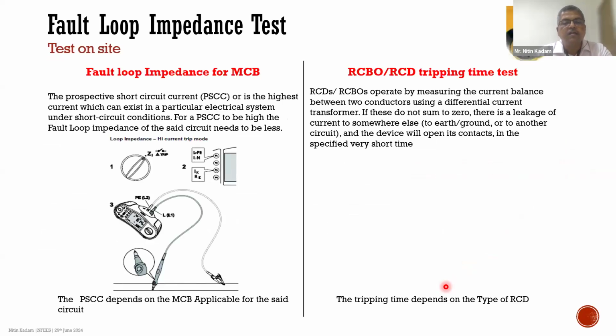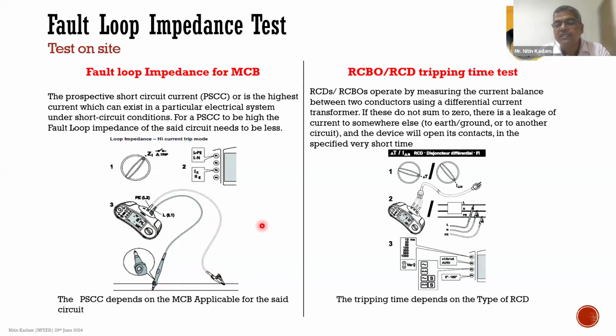So how do you do the fault loop impedance test on site? Basically, in case of MCBs, you have a multifunction tester available, which helps you to do the fault loop impedance test on the site. You have to connect the probes, one on line and the second one on the earth. And there are test buttons available, we'll see on the subsequent slides, to determine the prospective short circuit current that can be flowed in the earth fault loop that is created when there is an earth fault happening on the particular installation. In case of RCDs, it is required to test using the same multifunction tester the tripping time.